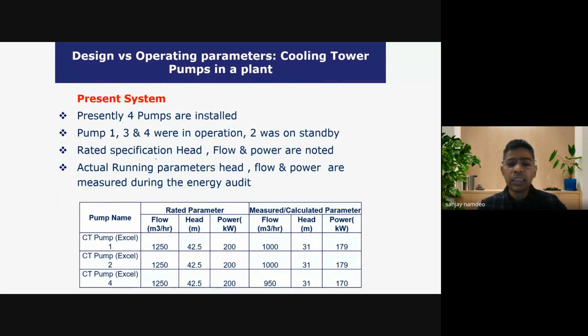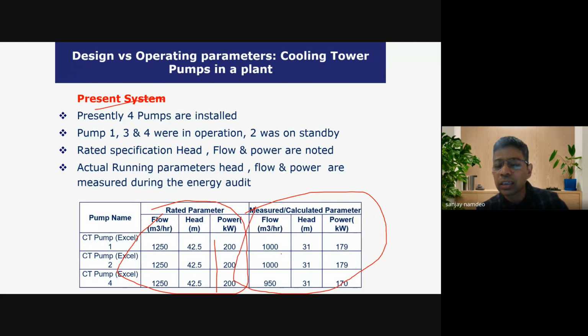Let us see. These are the 3 pumps installed in this plant, and you can see the rated parameters: 1250 meter cube per hour, 42.5 meter head, and this rated power of the motor. Actual performance parameters you can see here. These three pumps are delivering 1000 meter cube of flow. Operating pressure is 3.1 kg or 31 meter, and this pump is consuming 179 kilowatt. So these are the rated and the measured parameters.